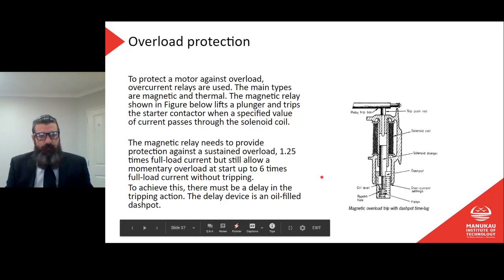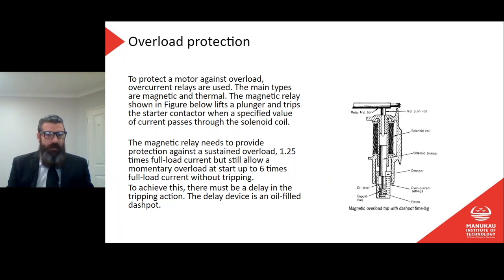Okay, overload protection for motors. To protect the motor against overload, overcurrent relays are used. The main types are magnetic and thermal. That rings a bell, huh? The magnetic relay shown in the figure below lifts a plunger and trips the starter contactor when a specified value of current passes through the solenoid coil. So this one's actually linked into our contactor, right? Our start and stop button with our contactor. We saw that in our circuit control unit. This is an overload that's linked into that.